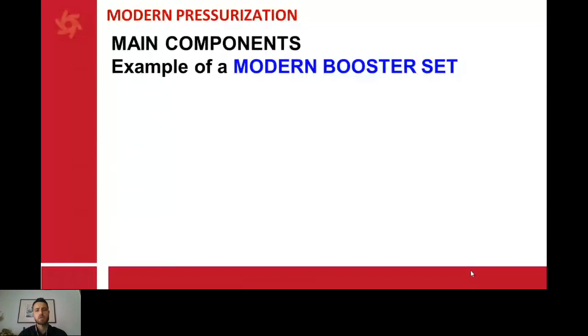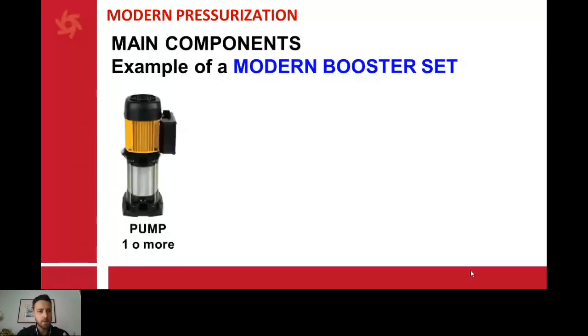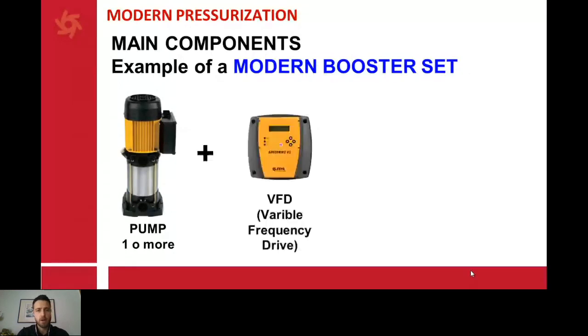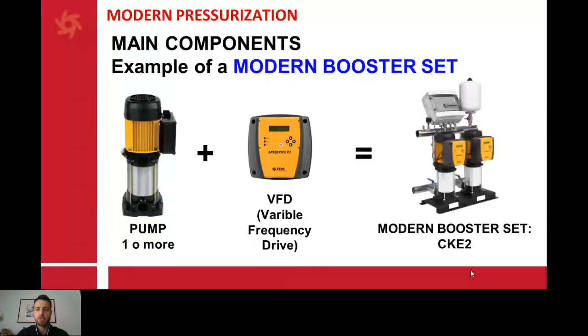What is a booster set? Actually, a modern booster set. Which are the main components? We are talking about two main components. It would be the pump, one or two or three or up to 8 pumps, and the VFD, variable frequency drive. This is the part that will control and automate the pump in order to get the modern booster set. This is an example of a 2-pump booster set called, in our case, CKE2.